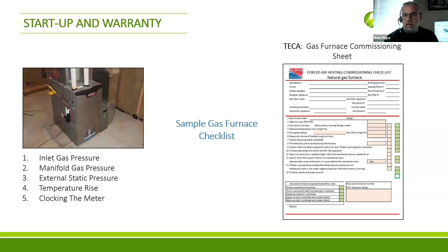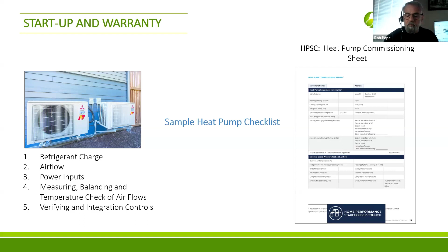If it's a heat pump, there's a heat pump commissioning sheet from the Home Performance Stakeholder Council, and HRAI and TECA each have one too. Some of the things on that form include refrigerant charge, airflow, power inputs, measuring and balancing, temperature check of airflows, and verifying integration of controls.